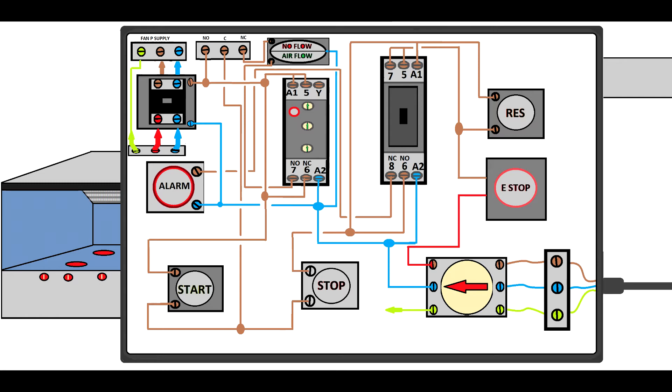Once I flick that switch, just follow this red line. It is going to the emergency stop, but the emergency stop is activated, so the power is not continuing the journey. I have live wire which goes into the emergency stop button but is not going further because when you press the emergency stop button, you should cut everything. Let's reset the emergency.